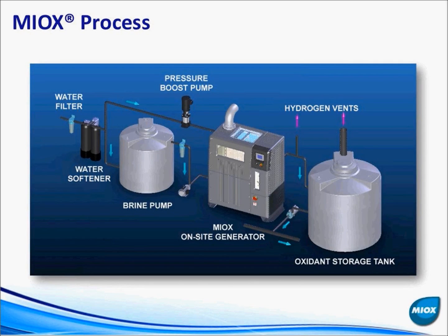On the left-hand side, we soften the water. Some of our smaller systems do not require softening, but larger systems do, because calcium can deposit on the electrolytic cell and become a maintenance issue. By softening the water, you condition it to get nice long runtimes with your electrolytic cell. We then split that stream.